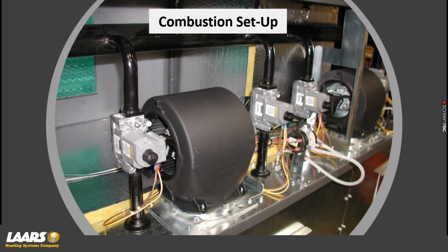Now, you'll see on the video I'm about to show, we have a single common gas train that comes into each gas valve. And you can use any one of the taps. You're going to have an Allen set screw on each gas valve. Any one of these you can use to measure incoming gas pressure. So for incoming gas pressure, which we'll see, you're going to have static pressure and running dynamic pressure. For your static pressure, read the rating plate of the boiler. We tell you 4 to 13 inches currently. The early version of this product, a couple years ago, was a 5-inch minimum. So we need to make sure we're within that range of 4-inch water column to 13-inch water column.